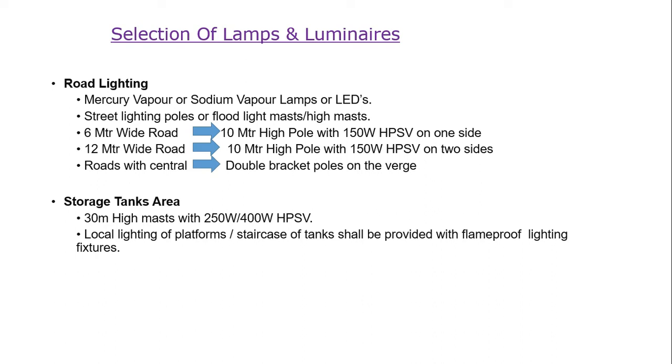We have to check whether 10 to 15 lux is the standard requirement for a street light. So whether with a particular spacing and a particular height with a particular light fixture, I am able to achieve that 15 lux on both sides of the road shoulder or not. On a standard basis, these are thumb rules, but we have to again cross verify these with respect to our project requirement in the calculation part.